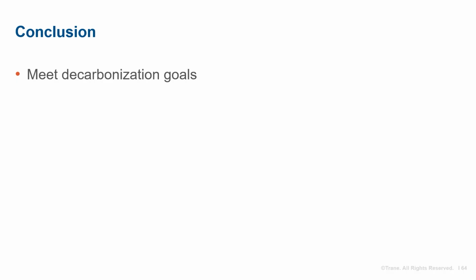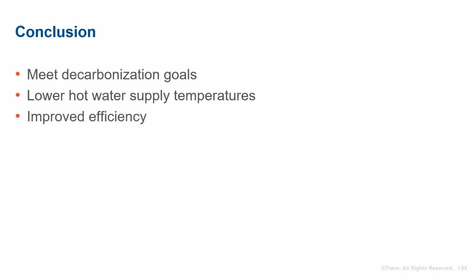In conclusion, retrofitting hydronic heating systems helps owners meet their decarbonization goals. Lower hot water supply temperatures are possible in existing buildings and improve system efficiency, capacity, and provide more unit options that may lower project costs. For buildings with terminal units that may not be capable of large cooling and heating coils, consider using adaptive or changeover coils with 4-pipe distribution using a distribution area director. As Ronnie showed, it can significantly lower project first cost.